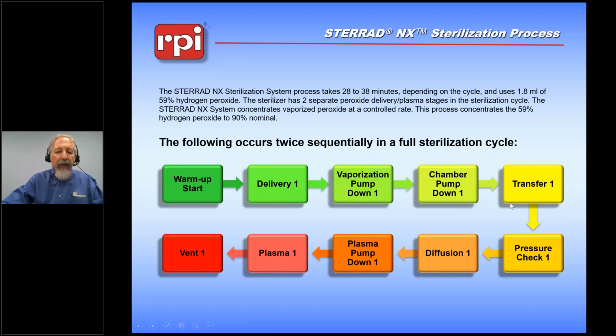And we transfer it. Okay, sorry about that. We pump down, we warm up all of these systems to make sure they are ready to go through our first run. We transfer the hydrogen peroxide from the vaporizer to the condenser. We check to be sure that the pressure is proper. We allow it to diffuse through the various lumens and the various hinges and spots within the material that's in the chamber until we finally feel it's been transferred and delivered, and then we turn on the plasma pumps to turn it into a plasma that breaks down the hydrogen peroxide, and then we vent it out to air. This process is done twice in each run, delivering approximately 1.8 mils of 59% hydrogen peroxide concentrated down to 90% nominal.